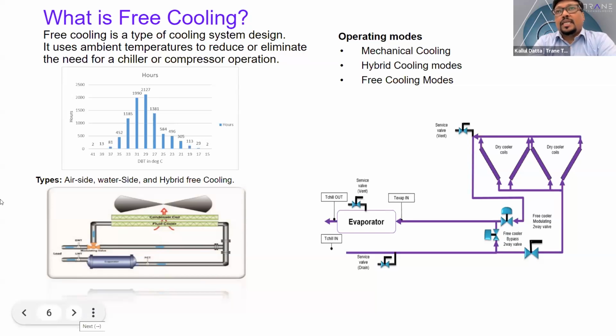Now, in case of hybrid cooling, the chilled water coming at 37 degrees from the load, instead of going directly to the evaporator, will first enter the free cooling circuit. The free cooling circuit ensures that heat transfer happens efficiently, because the outdoor air temperature is lower. The evaporator entering temperature, instead of 37 degrees, may be 36 or 36.5. So what happens if the entering water temperature drops? It reduces the workload on the compressor, and thus the chiller gains efficiency. When the compressor is working less, the chiller is obviously more efficient.